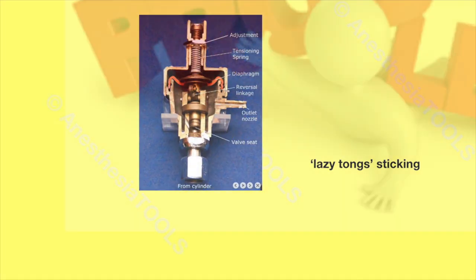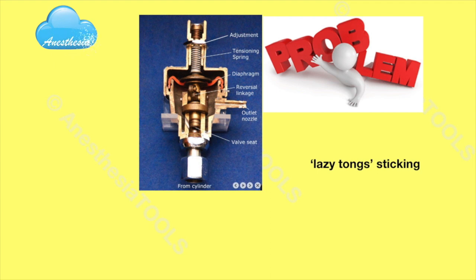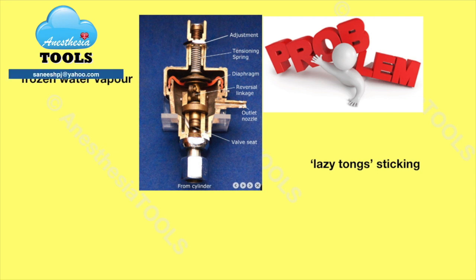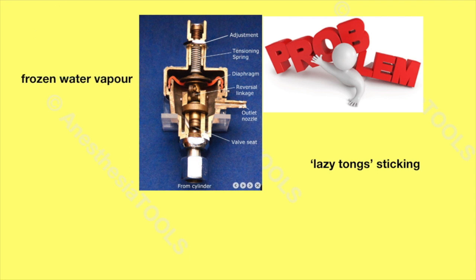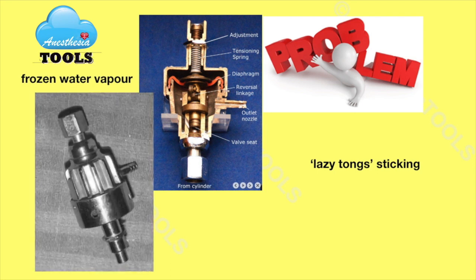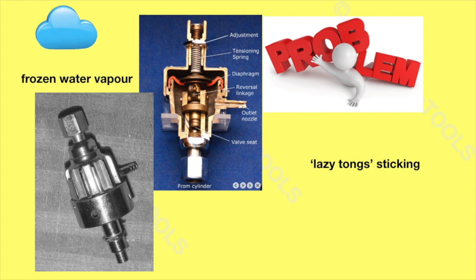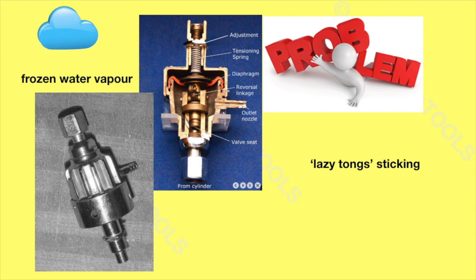There were some major issues with Adam's valve. Nitrous oxide loses heat on expansion, which chills the Adam's valve, causing it to become jammed in the open condition by frozen water vapor that tended to contaminate medical gases. Consequently, some Adam's regulators bore external fins to absorb heat from the surroundings, reducing the risk of this occurrence. Adam's valves sometimes developed a fault causing continual jumping of the flow meter bobbin due to the lazy tongs sticking from wear and tear, or from small particles of grit or metal in the lazy tongs or valve seating.